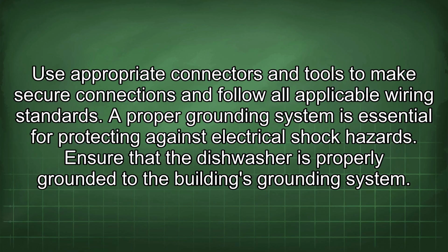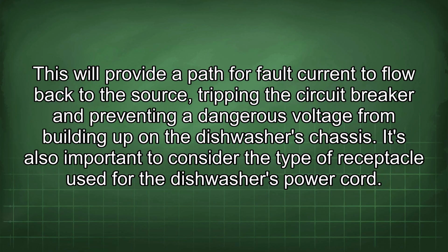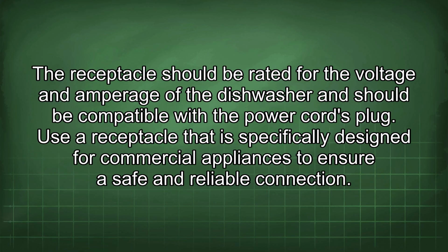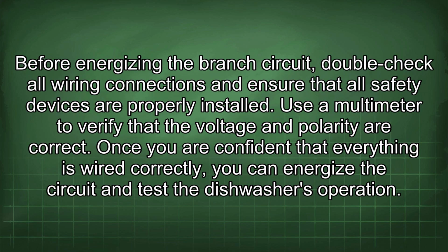A proper grounding system is essential for protecting against electrical shock hazards. Ensure that the dishwasher is properly grounded to the building's grounding system. This will provide a path for fault current to flow back to the source, tripping the circuit breaker and preventing a dangerous voltage from building up on the dishwasher's chassis. It's also important to consider the type of receptacle used for the dishwasher's power cord. The receptacle should be rated for the voltage and amperage of the dishwasher and should be compatible with the power cord's plug. Use a receptacle that is specifically designed for commercial appliances to ensure a safe and reliable connection. Before energizing the branch circuit, double-check all wiring connections and ensure that all safety devices are properly installed. Use a multimeter to verify that the voltage and polarity are correct.